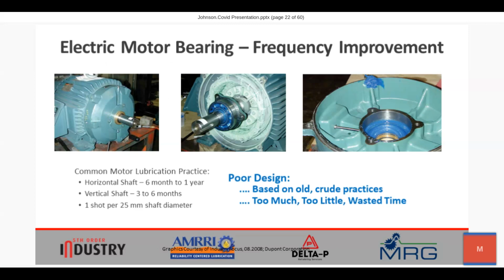It's very common practice in industry to take the old standby. We lubricate motors every 6 months or a year. If it's a vertical shaft, perhaps we lubricate at 3 to 6 months. And we use kind of a nominal value, 1 shot, whatever that may mean, of grease per each 25 millimeters of shaft diameter. Well, this is a poor design based upon a crude understanding of grease failure modes. It's either too much or too little, and in many instances, a substantial amount of wasted time.